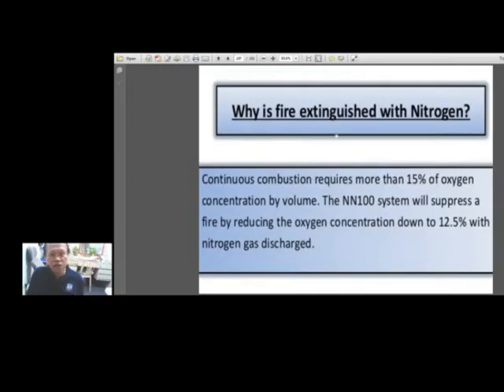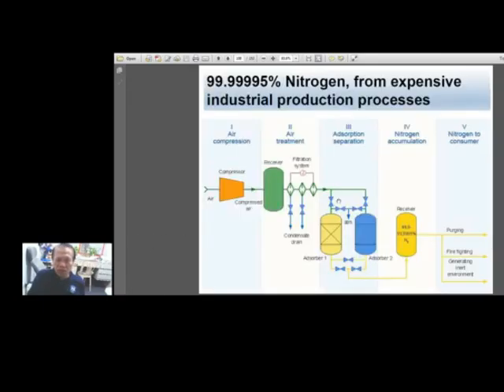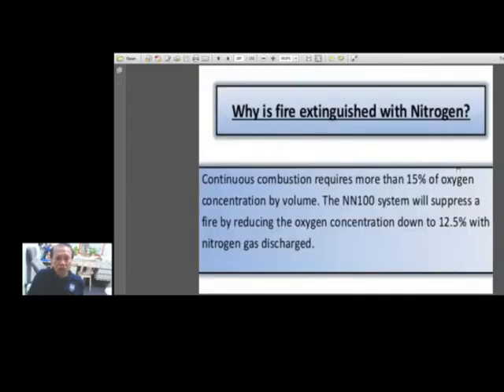Why is fire extinguished with nitrogen? Continuous combustion requires more than 15% of oxygen concentration by volume. The NN100 system will suppress a fire by reducing the oxygen concentration down to 12.5% with nitrogen gas discharge. Let us see this, no? So this is the NN100 system that it mentions.